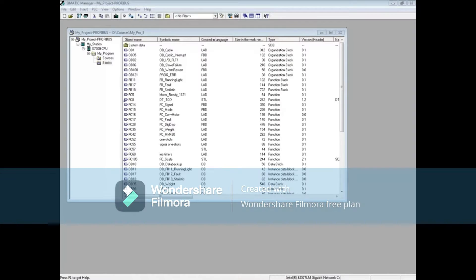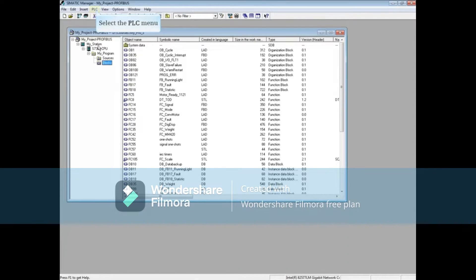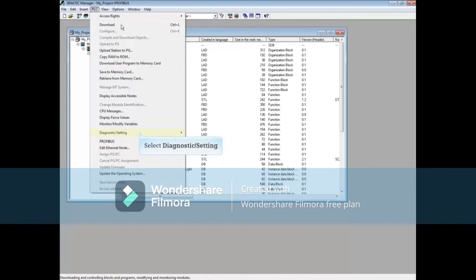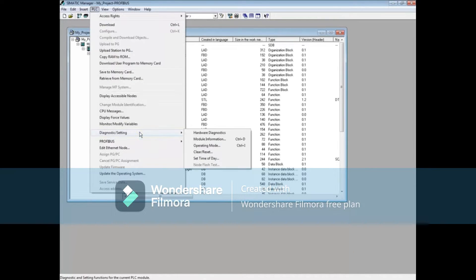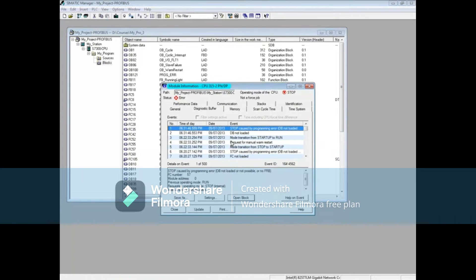We will now show you how to access the different tools. The first tool we will look at is the module information tool. In SIMATIC Manager, highlight the blocks folder, select the PLC menu, and choose diagnostic settings, then click on module information. You can also launch this tool by holding down the Control key plus the D key.